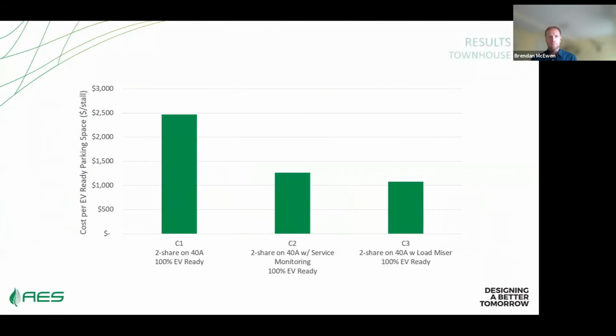And then this is the results for the townhouse. By implementing load switching with a load miser, sharing a branch circuit between a dryer and the EV charging, we avoid a panel upgrade that you would need with service monitoring or just with a dedicated circuit into the parking space. Even with that relatively more expensive piece of control equipment, it reduces the whole cost significantly.